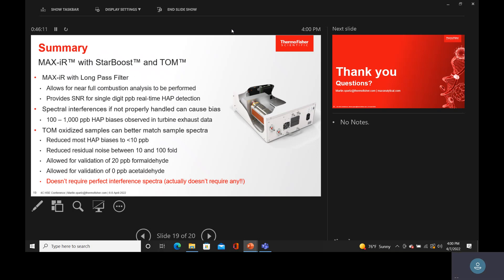This is all brand new — there's some content on the website and a brochure for the formaldehyde stuff, but this whole analysis is literally not even a week old. There's still more we can do, but the point is — I challenge anybody to get below 1 ppm on a standard FTIR in that spectral region, just because of the water. You'd have to take just a few points and not look where the water is at all. It's a hard measurement because the water interference is just so intense.